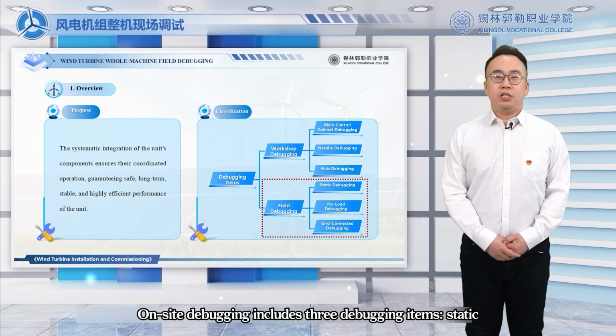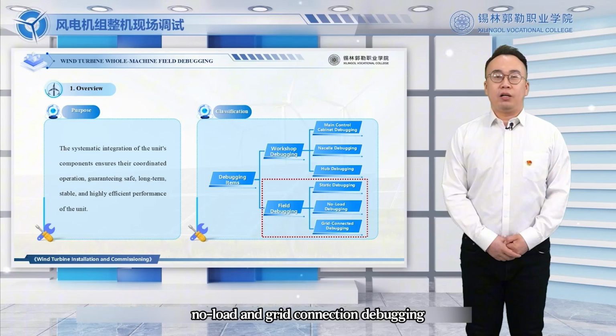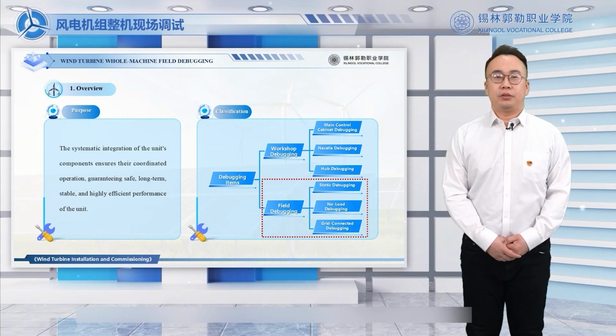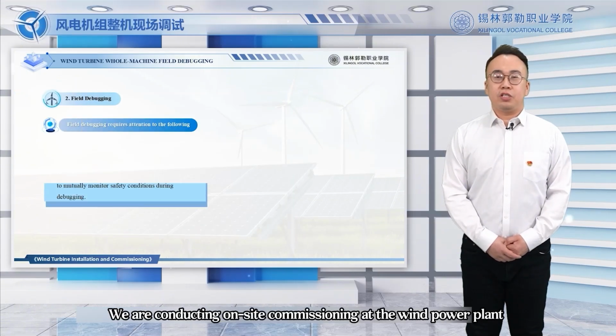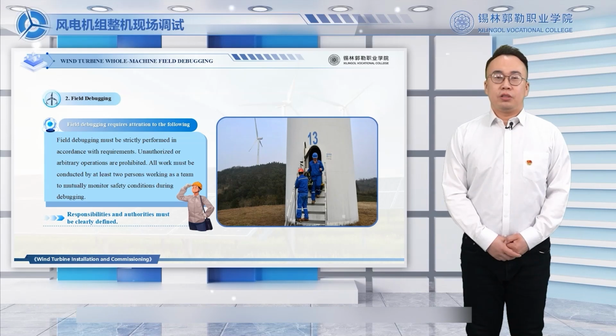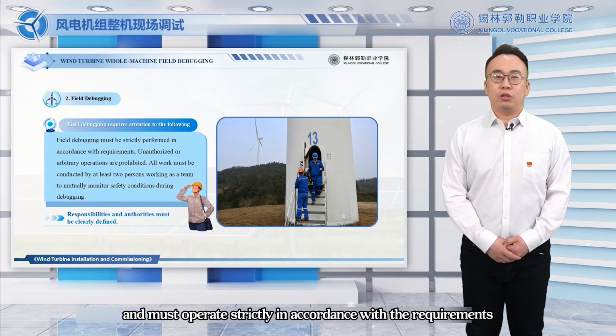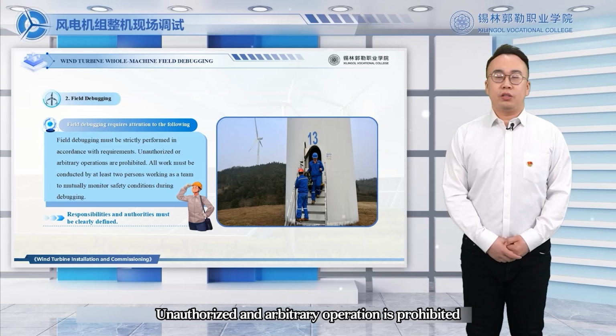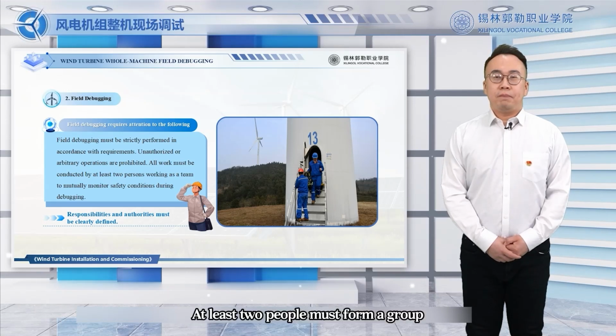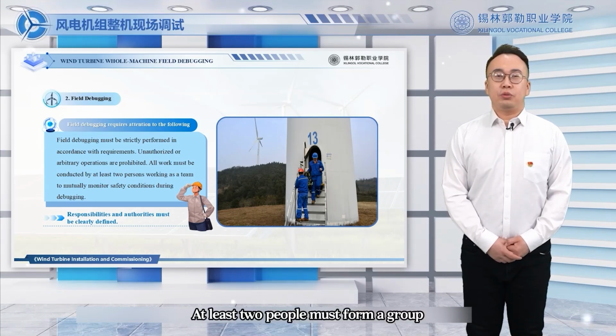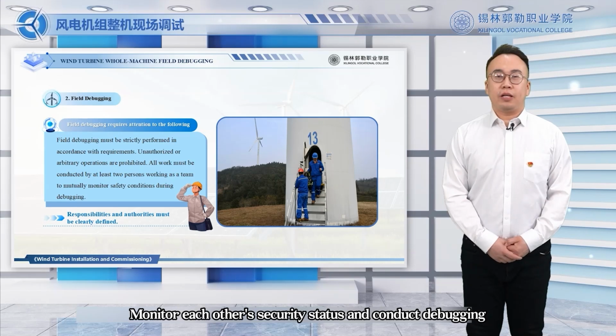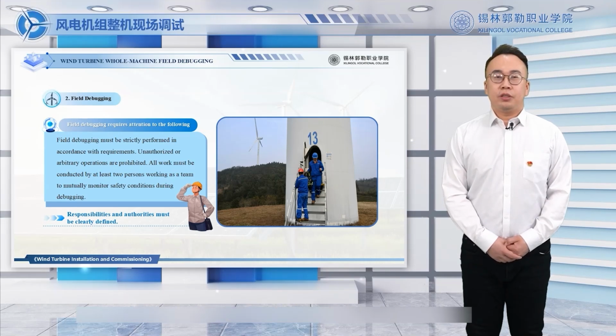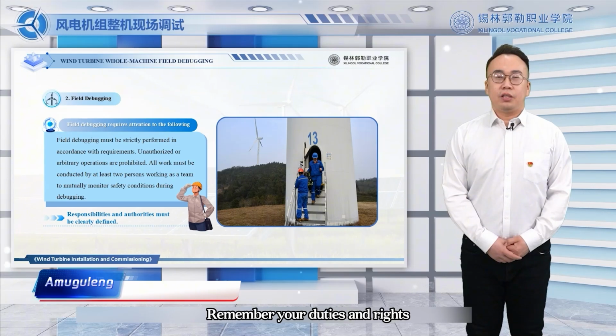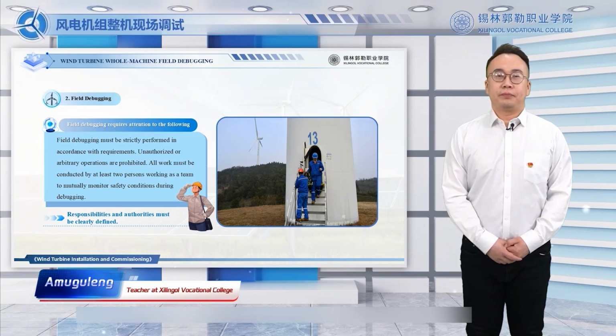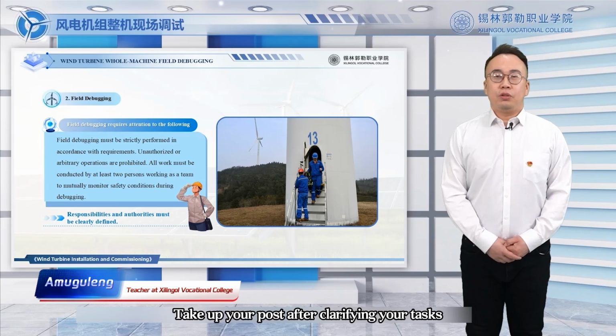On-site debugging includes 3 debugging items: static, no-load, and grid connection debugging. We are conducting on-site commissioning at the wind power plant and must operate strictly in accordance with the requirements. Unauthorized and arbitrary operation is prohibited. At least 2 people must form a group, monitor each other's security status, and conduct debugging. Remember your duties and rights. Do not operate beyond your authority. Take up your post after clarifying your tasks.